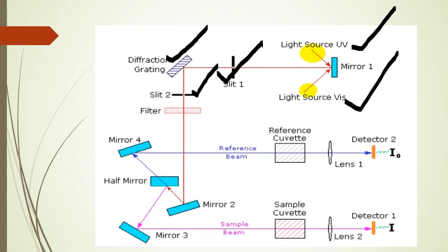So this is the diagram of the double beam UV visible spectrophotometer. Here is the light source. You can see very clearly the UV and visible light source, whose light goes through the mirror, and we have the slit through which it passes. Here the diffraction grating plays the role of monochromator, and here slit 2 lets the light pass, and here is the beam chopper, which converts the beam into two equal halves.